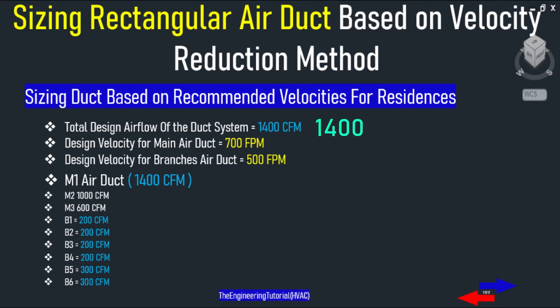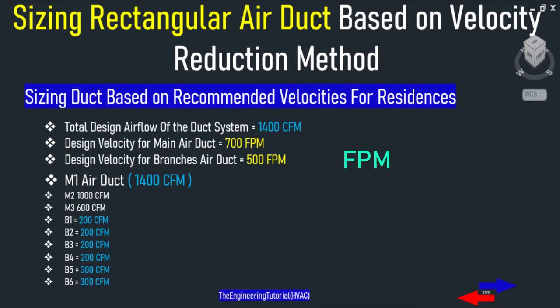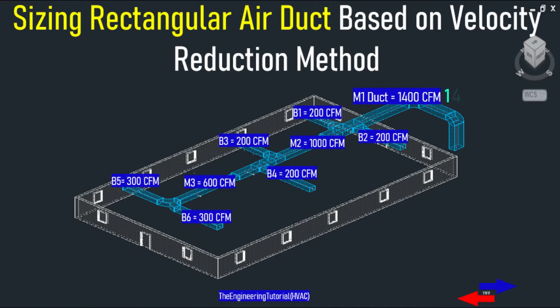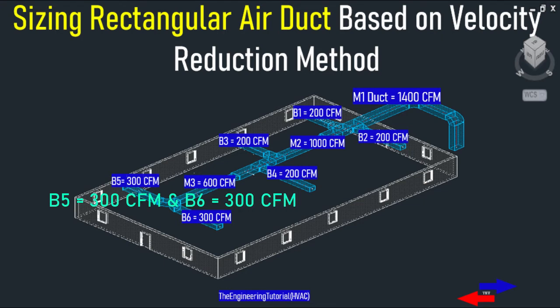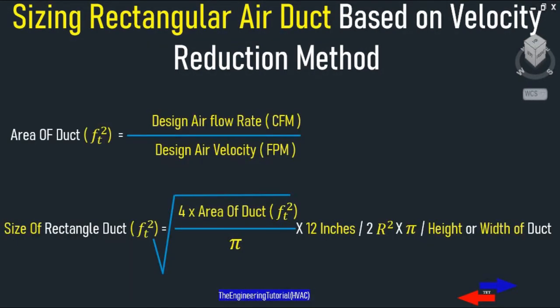For the example, there is a design airflow rate of 1400 CFM and we have been asked to find the sizes of rectangular air ducts at the recommended velocities of 700 FPM for main duct and 500 FPM for branch ducts. As you can see in the example, 1400 CFM flows through the main duct, minus 400 CFM for B1 and B2, leaving 1000 CFM for M2. Again minus 400 CFM for B3 and B4, leaving 600 CFM for M3, minus 300 CFM for B5 and 300 CFM for B6.